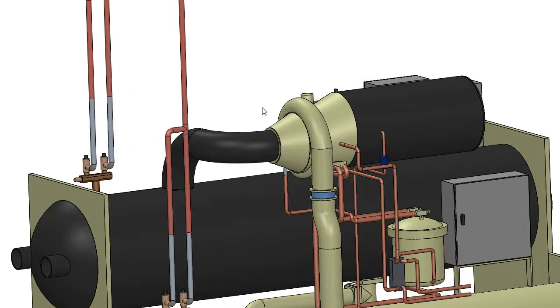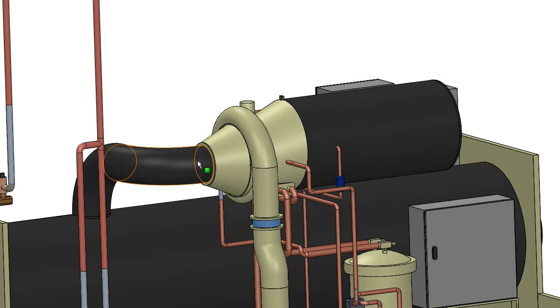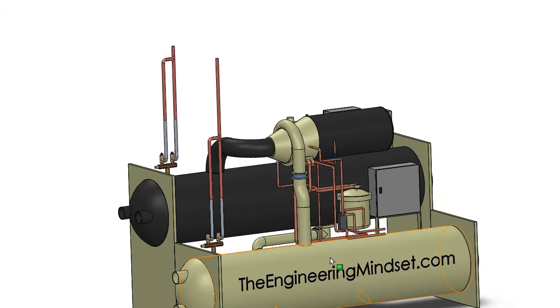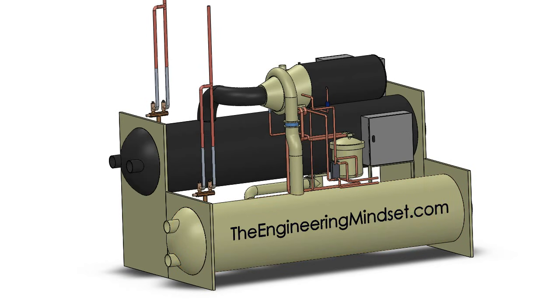Now the compressor, as you should know by now, is mounted up here on the top of the chiller, and it's being fed on the suction line here from the evaporator. That's the refrigerant leaving there, boiling off and entering through the suction line into the compressor, just passing through the vane guides here. And the refrigerant's then going to enter the compressor. It gets spun around at high velocity and compresses in the volute here, and then that gets sent down into the condenser here, and the heat is then rejected from this and off around the building.